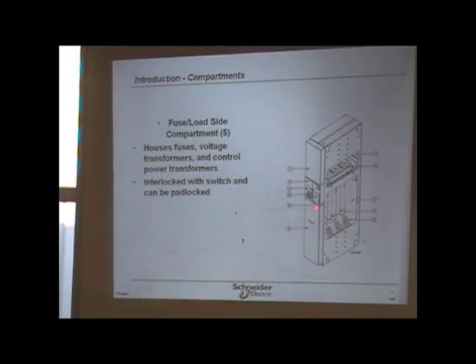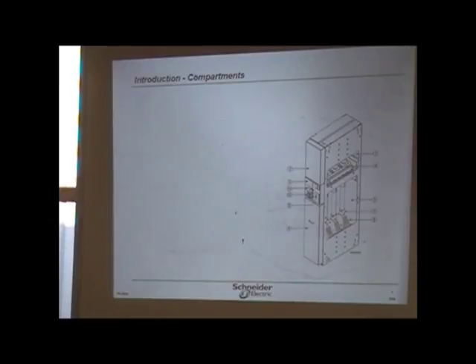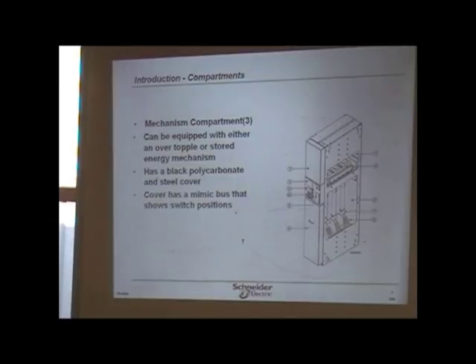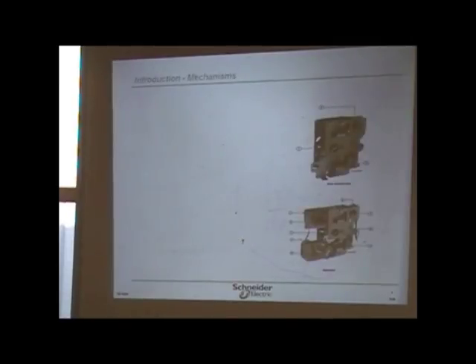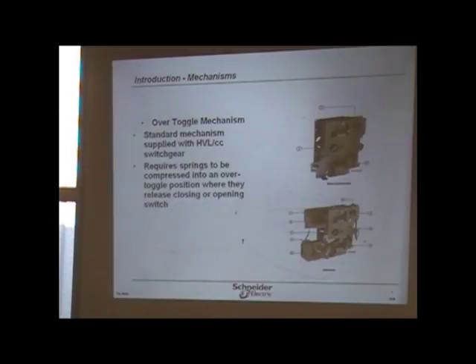The load side, as far as the fuses, we talked about how you can actually twist and turn, pull them out, pull them in. Yeah, that's the mechanism compartment that we were talking about. So we saw the mechanism right there, what it could look like. It's called an over toggle mechanism, and that's a standard. It's supplied with the HVL CC switchgear. It's spring compressed, and the blade is independent of the operating speed because of the spring. So regardless of how slow I go, the minute that spring takes over, it slams it in, right.